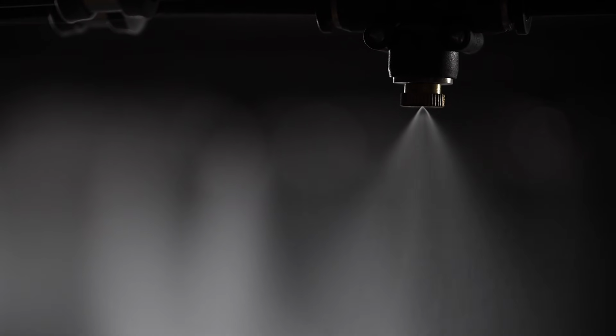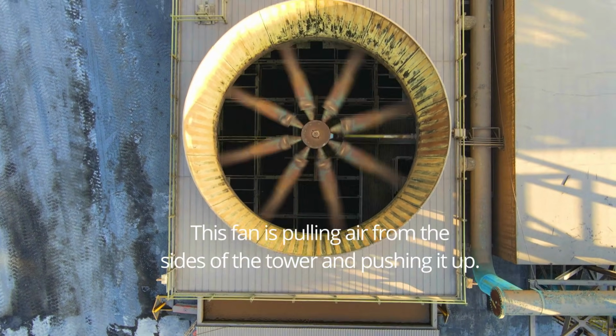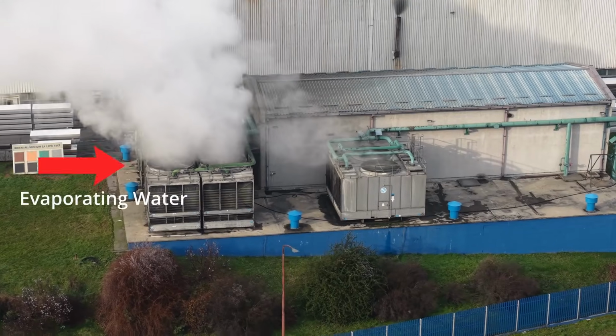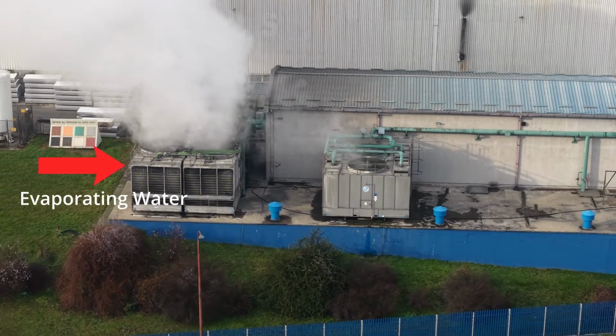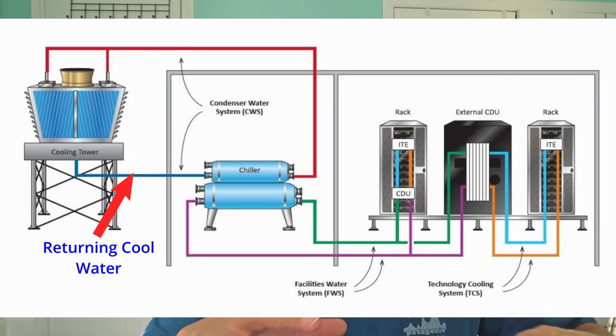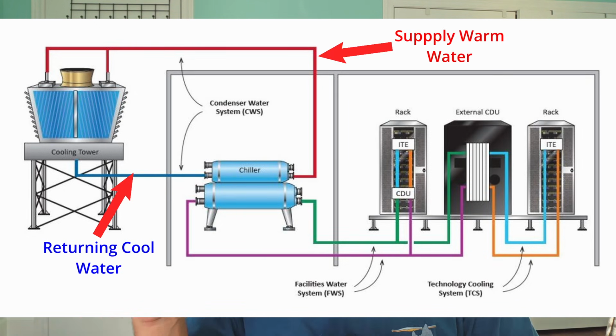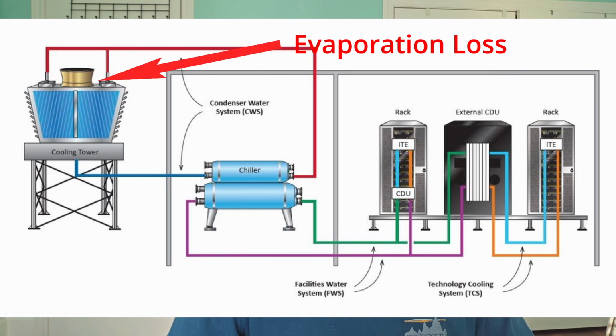In order to reject the heat generated by the data center and to cool the condenser water down, an open cooling tower turns the entering condenser water into a fine mist, essentially increasing its surface area. Then the cooling tower fans blow atmospheric air up through the mist, evaporating 1 to 2% of the total mass of the condenser water. This evaporation results in an overall reduction in temperature for the rest of the condenser water. The remaining water is then circulated back through the loop again to collect more heat from the chiller. So as you can see, 1 to 2% of the water is lost in the process every time the water goes through the cycle. And this water has to be made up by a fresh water source continuously.